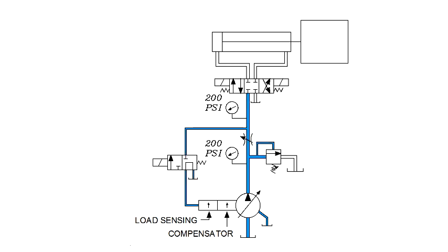Check the pump documentation to find the correct pressure. Usually, the load sensing valve is factory preset to about 200 or 300 psi, and no adjustment should be required. In practice, however, we could either suffer the effects of the plant knob turner, or the spring could lose tension over time. In our example, we will be setting the load sensing valve to 200 psi.